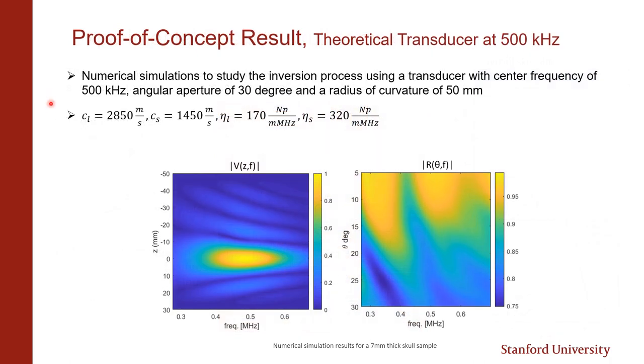Therefore, to have a better confidence in inverting material properties of skull samples, a proof-of-concept numerical simulation is performed at 500 kHz, assuming the attenuation in the skull is twice as the number for the plastic samples. And the inversion process is validated numerically here, the reflectance function of the skull is accurately inverted as shown, and the numerical simulation results demonstrate the ability of the acoustic microscopy system that's operated at 500 kHz to accurately invert the acoustic properties of the skull. We are currently in the process of building a few acoustic microscope prototypes at 500 kHz.